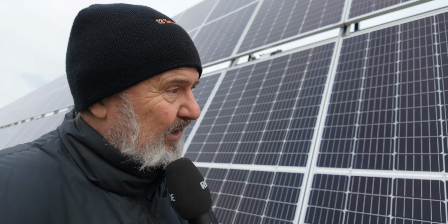So we've put this array here - there's a couple of these - 68 kilowatts of tracking solar, and it's got currently 4 times 80 kilowatt hour usable battery stacks connected to it. So what's that? 320 kilowatt hours of storage currently connected to the Solis 50 kilowatt hybrid. That gives us a lot more storage. The original microgrid system was 152 kilowatt hours, and so now it's kind of semi-retired. It basically provides a grid forming voltage, so it's a voltage source, and the Solis 50 kilowatt hybrid is now the current source for all the loads.